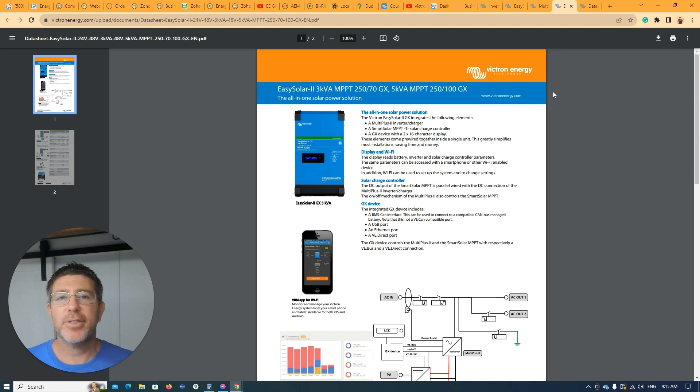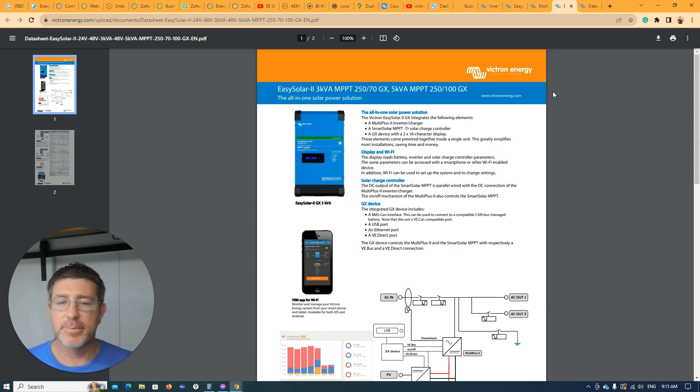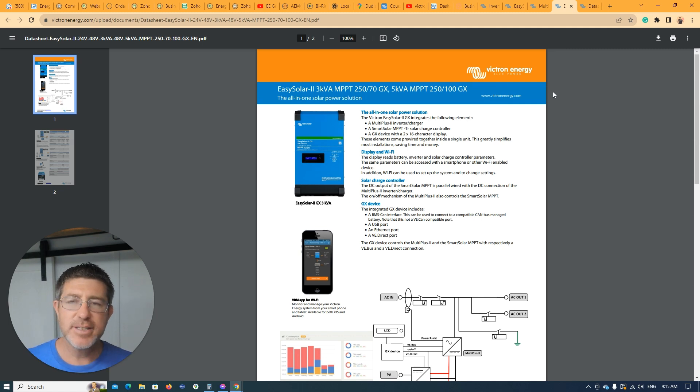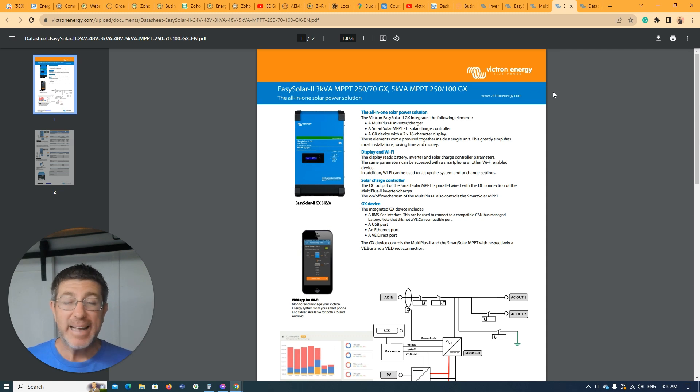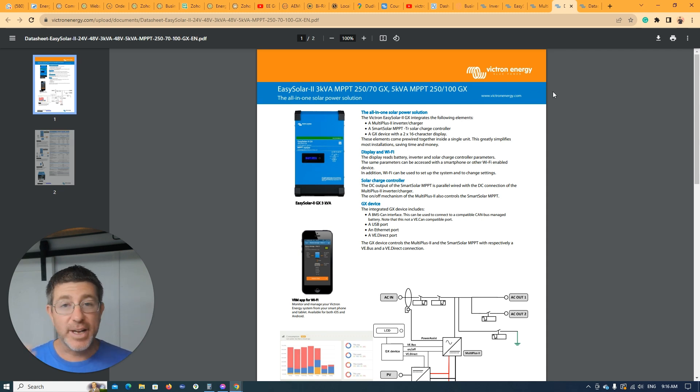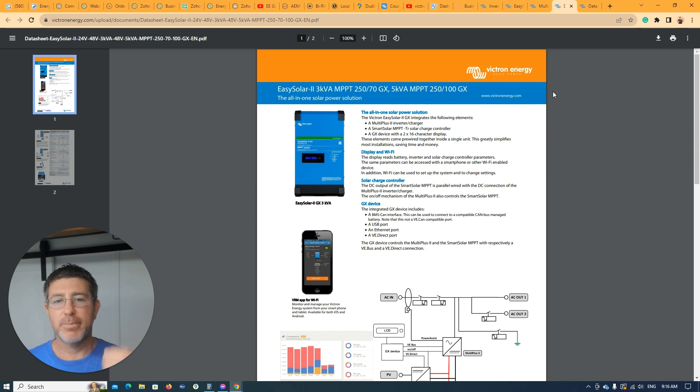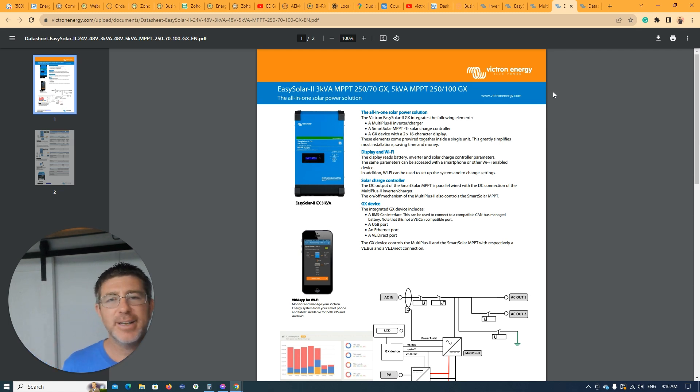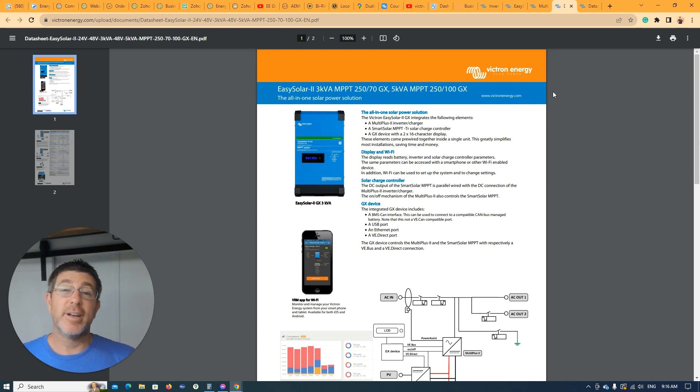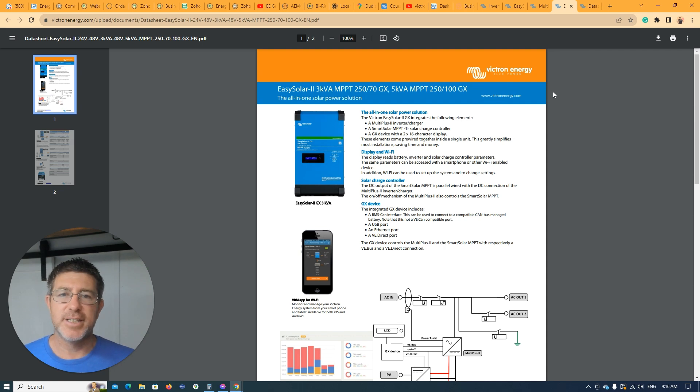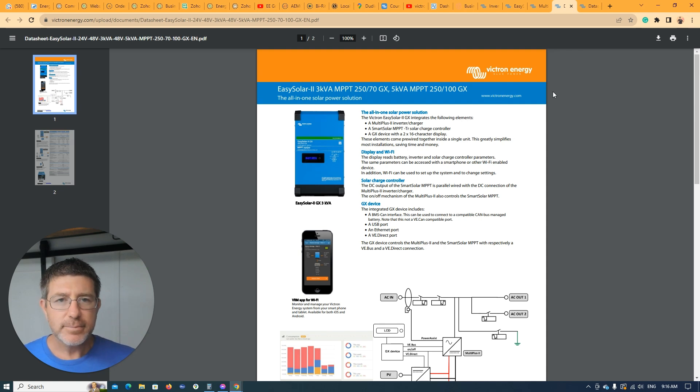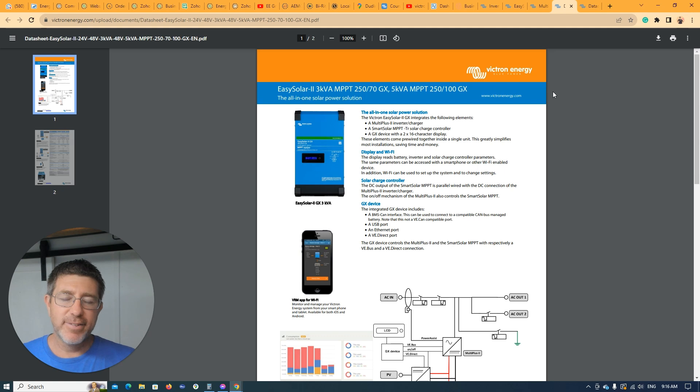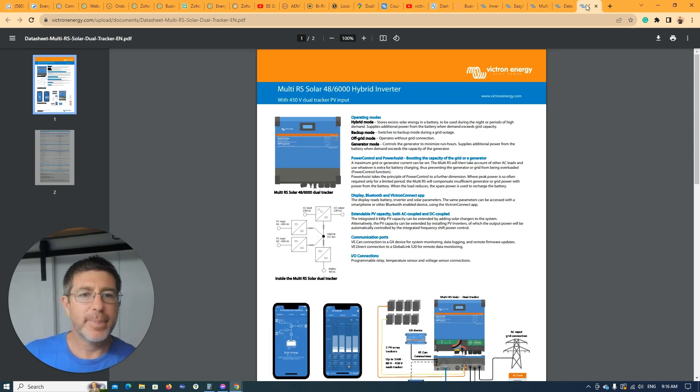Besides that, they've been a really good unit when we've used them in the right application for the right situations. They can be used for three phases as well, but you can't parallel them. So you can actually only have one inverter on each phase. And what I would actually recommend from an easy solar point of view, you'd use one easy solar on phase one and use a multi-plus on phase two and phase three to make all that work. You don't have three Venuses in the situation in each system. I would just use one, use an easy solar as one on the main phase, and then have a multi-plus on the other two phases.